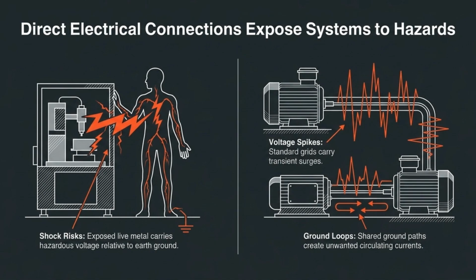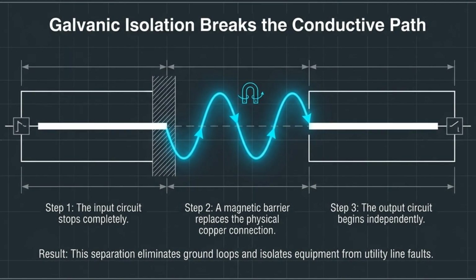Direct electrical connections expose systems to hazards. These include shock risks from exposed live metal and system damage from voltage spikes and ground loops, which create unwanted circulating currents. Galvanic isolation breaks the conductive path in 3 steps. The input circuit stops, a magnetic barrier replaces the physical connection, and the output circuit begins independently. This separation eliminates ground loops and isolates equipment from utility line faults.